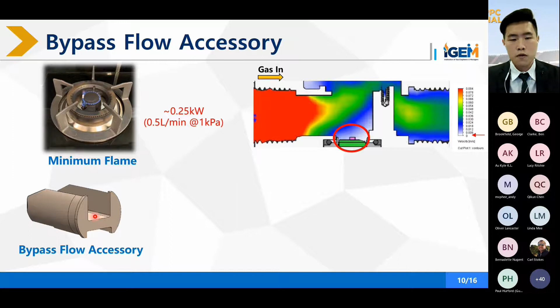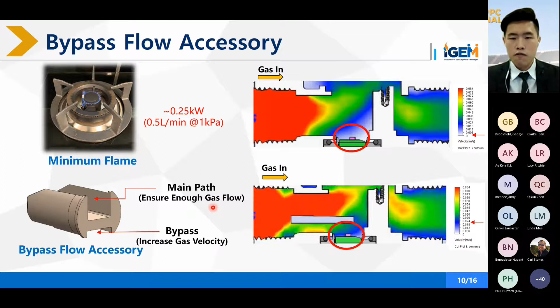To tackle this problem, I've designed a bypass flow accessory to separate the gas into two paths. The main path ensures enough gas flow to support the appliance maximum rating, while the bypass increases the gas velocity by covering the sensor surface. So after inserting the bypass flow accessory, you can see there is an improvement in the gas velocity above the sensor. And this will help the thermopiles generate the temperature difference and consequently improves the sensor's sensitivity for the minimum flame operation. And with this simulation backup, we finally adopted the MEMS flow sensor and finalized our product design.